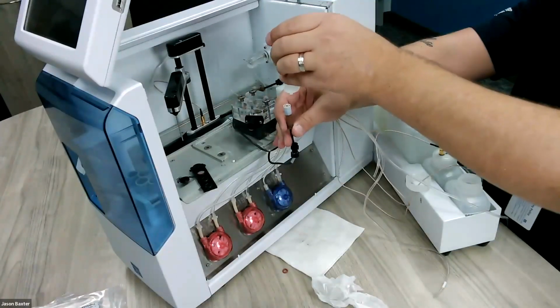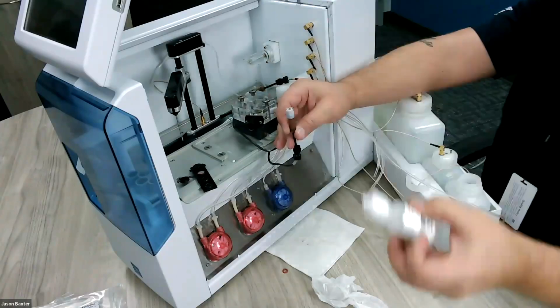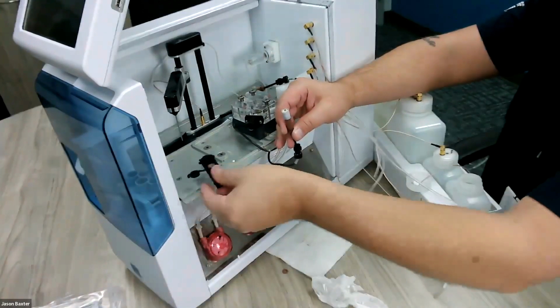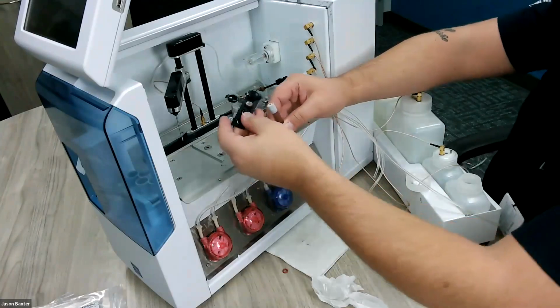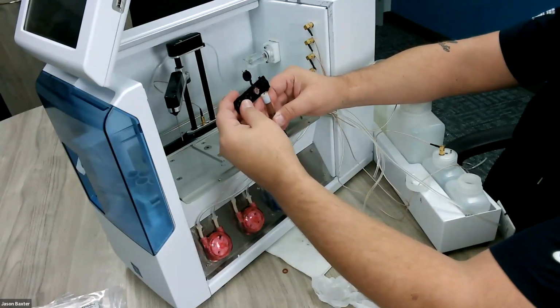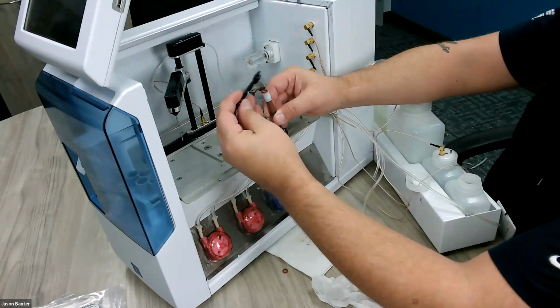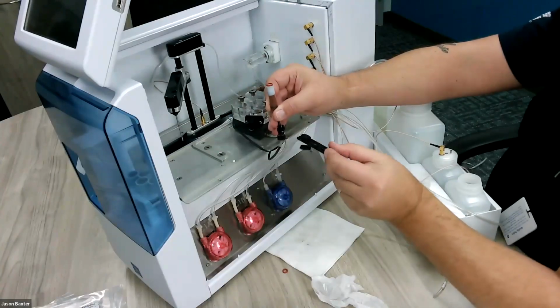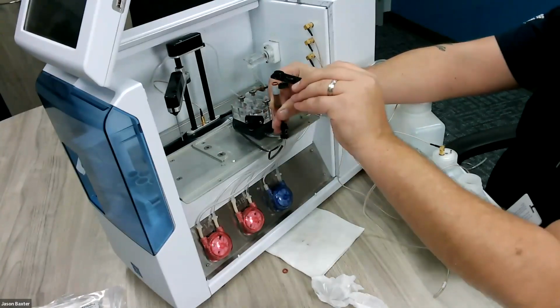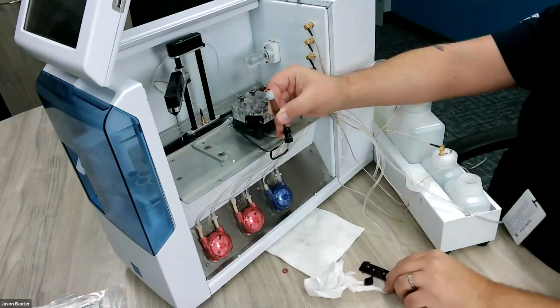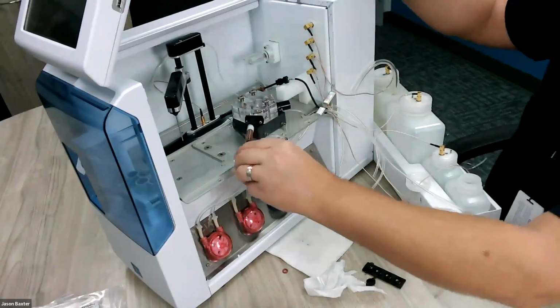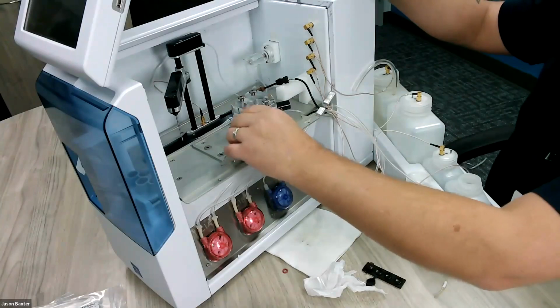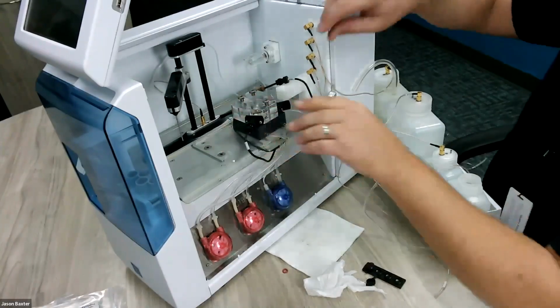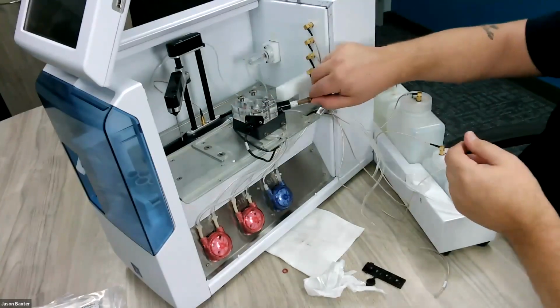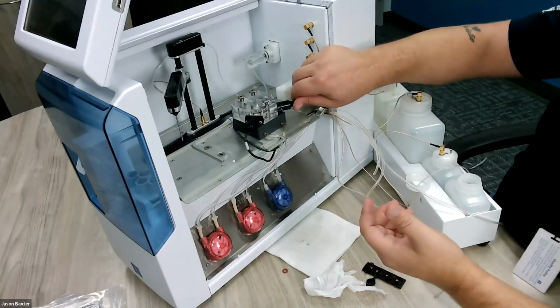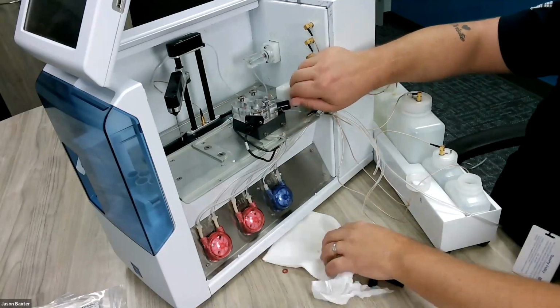Get out your sodium chloride, put about 3 drops onto the top face of that electrode. I'm trying to do this in a way that can be seen by the camera. This is backward from how I normally do it. Let the membrane fall out of the membrane housing and then use the backside of the membrane holder to snap it into place. Then you can reinstall. And obviously you're going to do the same with this one. I don't have a membrane installed on that one on purpose, just for sake of time.